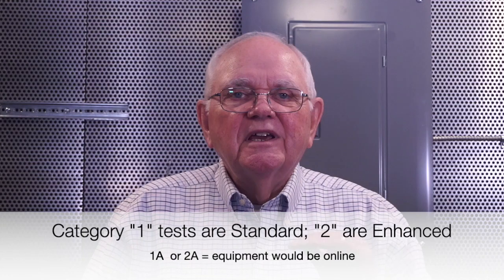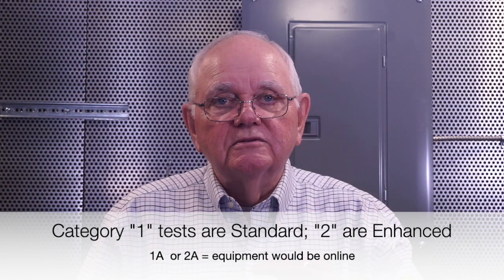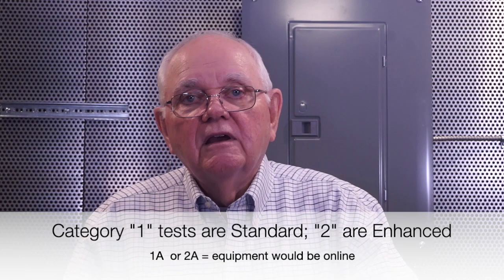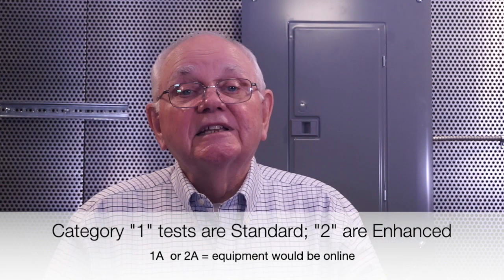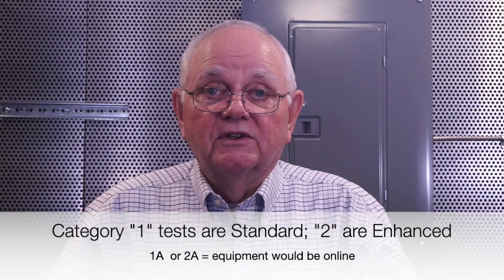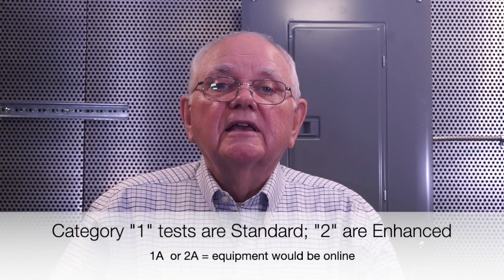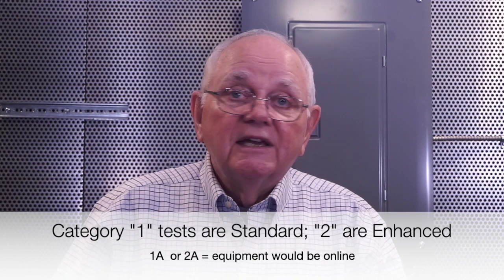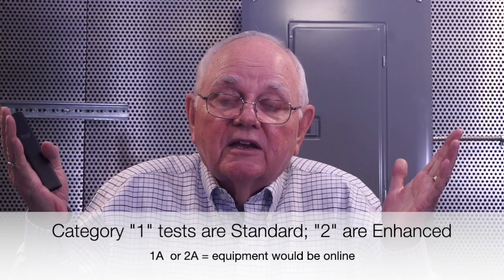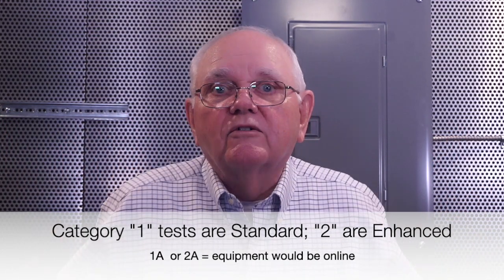Now, as far as what you're going to run into for this testing is the different categories of testing. You're going to see throughout 70B, it's going to tell you, well, for this equipment, do a Category 1 test. Or do a Category 1A test on it. All that means is Category 1 or Category 2 means that the equipment's offline. Category 1A or 2A means that the equipment is online while you're doing the testing. And then Category 1, whether it's 1 or 1A, it's our standard test, our routine test we've been talking about and just demonstrated on that motor, right?